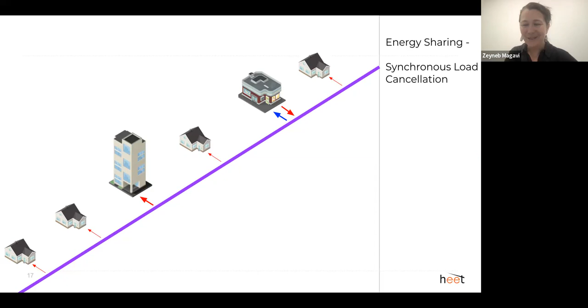And if you add the boreholes, and you will, you have another phenomenon whereby there is an ability to load cancel asynchronously. So perhaps the most extreme version of this is, here we are in the middle of the winter, everybody's heating and we're dumping heat into the ground. And then, oh, yeah, my slide didn't work. Right, one moment. The most extreme example is dumping heat into the system in the summer and pulling it out as it gets colder to heat. And that has been documented in some systems.